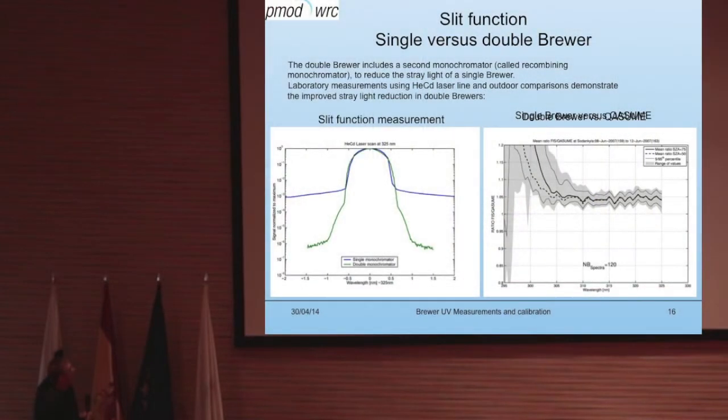Well, here, this figure over here is made with this subtraction of the stray light the way I just explained it, by taking away these 2 nanometers. And even with this method, you can see that you're still having a lot of stray light. So if you don't apply any stray light correction, I don't even want to know how that would look. And this here, this 10, 15%, around 300 nanometers, will not affect your dose that much. But a stray light correction has already been implemented on that graph.